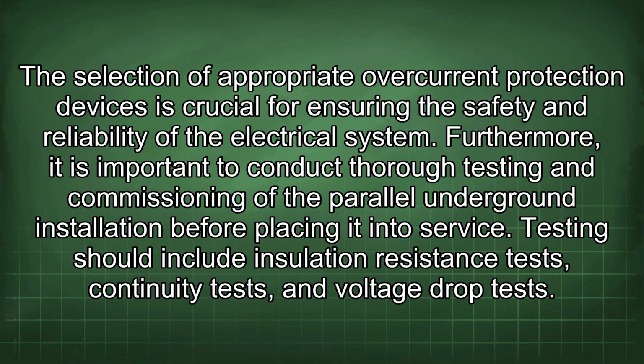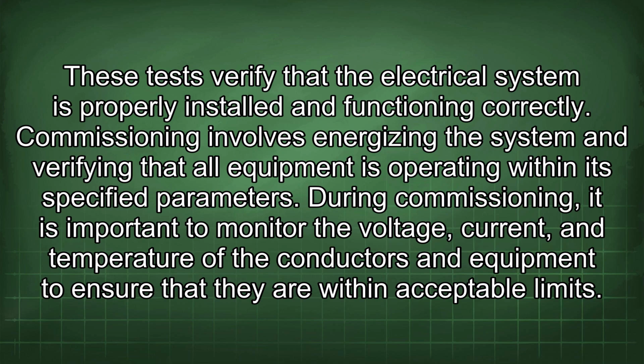Furthermore, it is important to conduct thorough testing and commissioning of the parallel underground installation before placing it into service. Testing should include insulation resistance tests, continuity tests, and voltage drop tests. These tests verify that the electrical system is properly installed and functioning correctly. Commissioning involves energizing the system and verifying that all equipment is operating within its specified parameters. During commissioning, it is important to monitor the voltage, current, and temperature of the conductors and equipment to ensure that they are within acceptable limits.